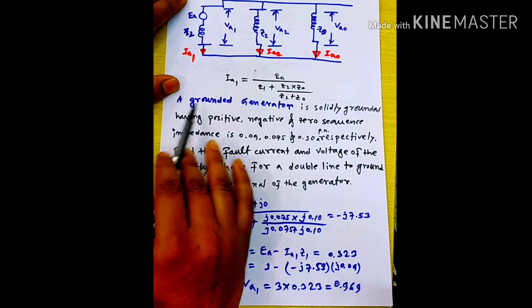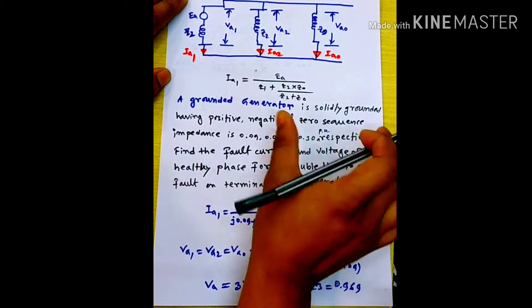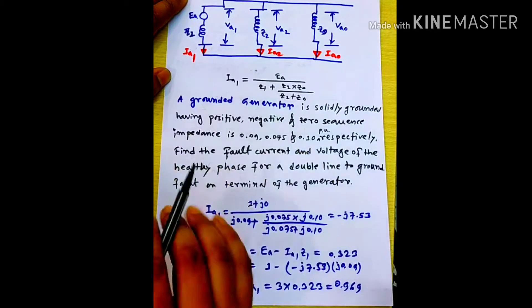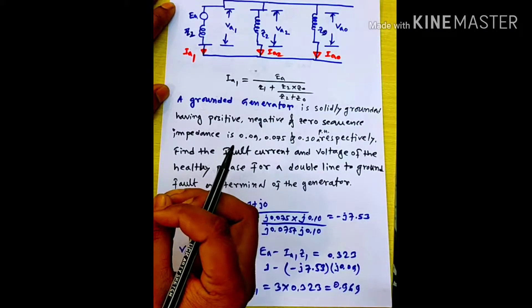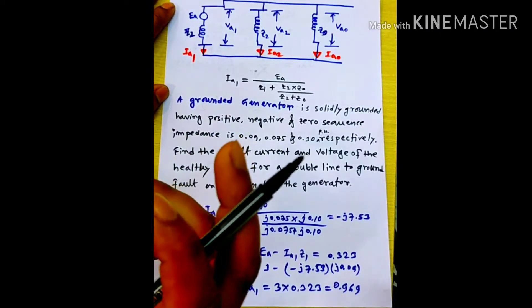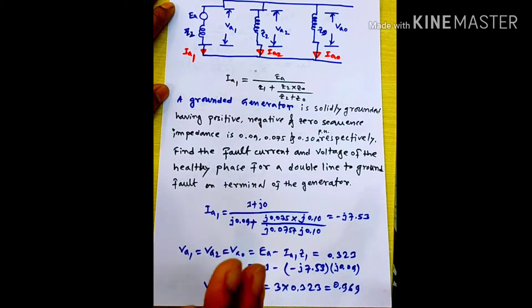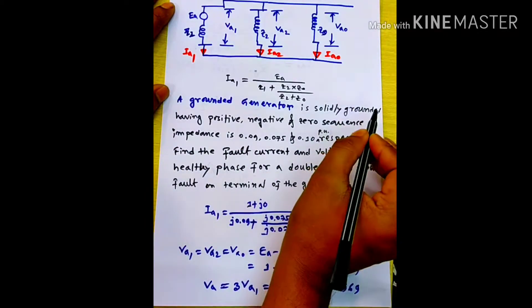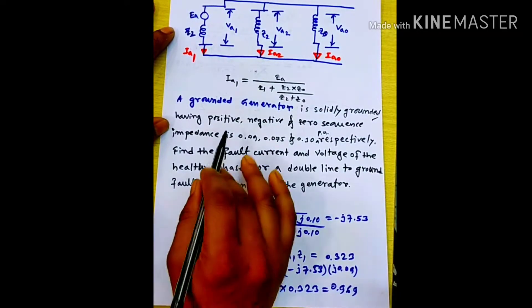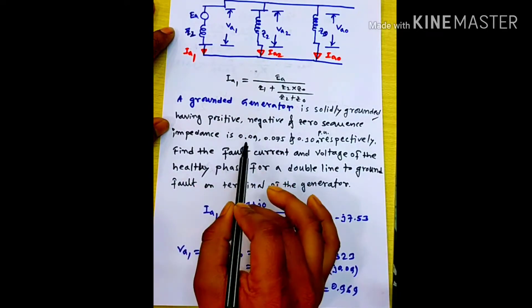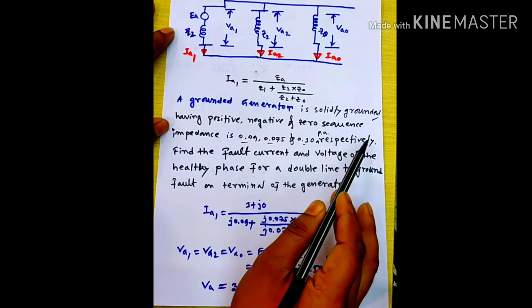This grounded generator is solidly grounded. When the generator neutral is grounded, we are not going to use a grounding resistor or reactor — we are going to be solidly grounded. A solidly grounded generator has positive, negative, and zero sequence impedance, given per unit respectively.